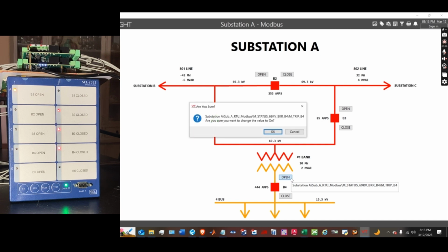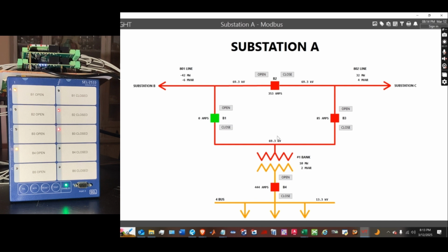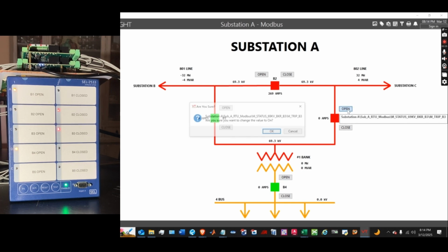B4 is open next, and we see its current go to 0, along with breaker B3's current and the megawatt and megavar flow through the transformer. The transformer high side voltage remains at 69.3 kV. After opening breaker B3, the high side voltage goes to 0, as there is no longer a connection between the transformer and the power system.